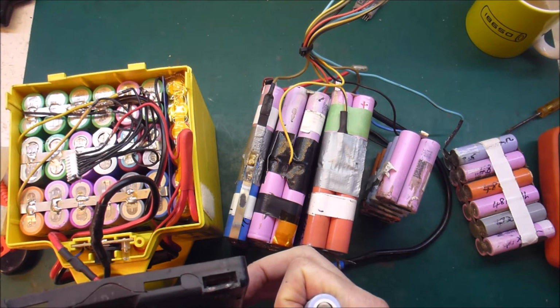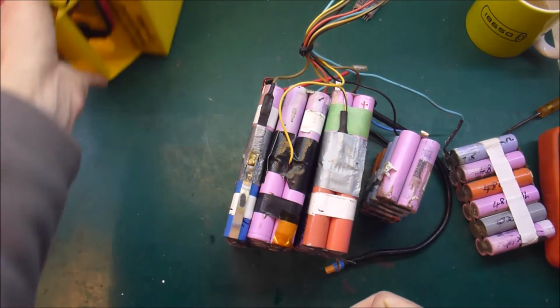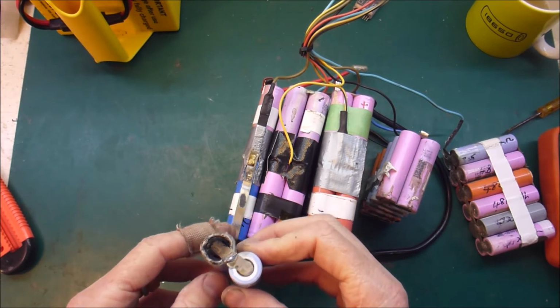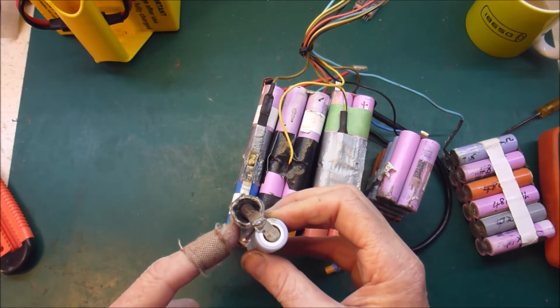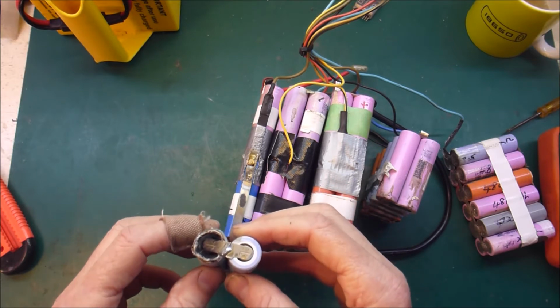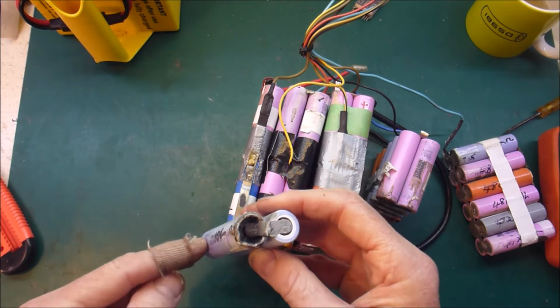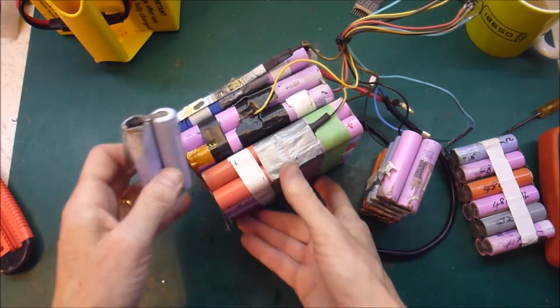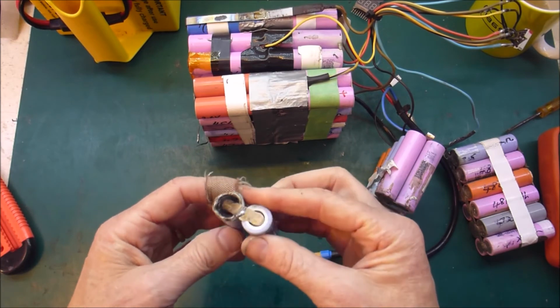What does that mean? What conclusion can you draw from that piece of information? Is it the fact that the other fuses blew and this fuse didn't blow and therefore it vented? Or did this overheat and then short, causing the fuses to blow? That is something I don't know. I don't know which way around the cascade of failures occurred.